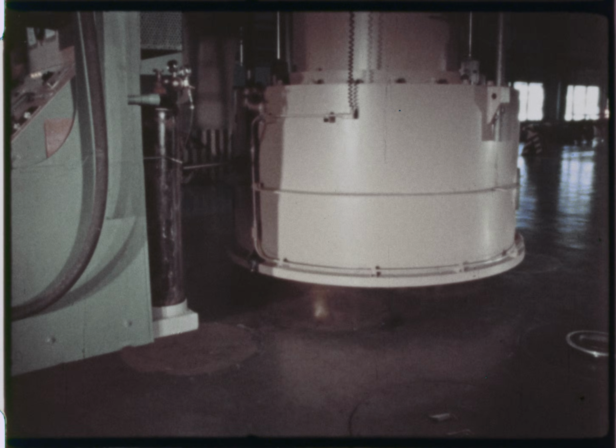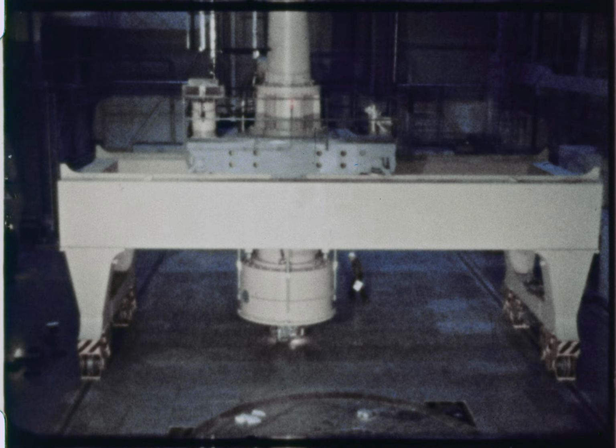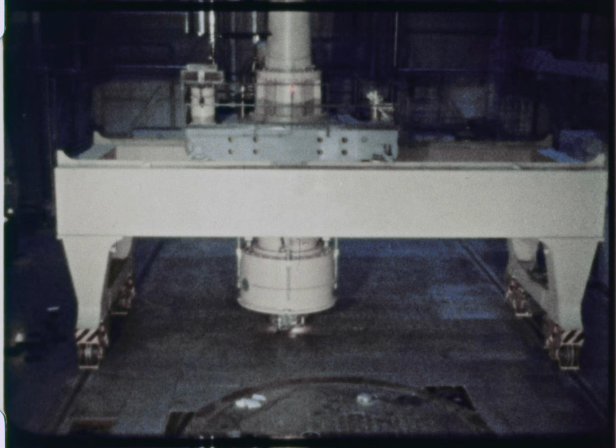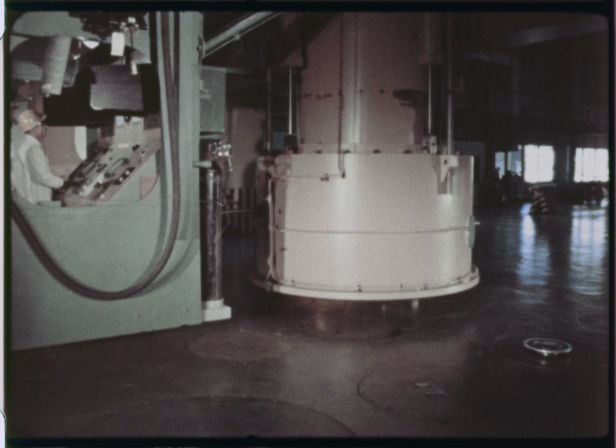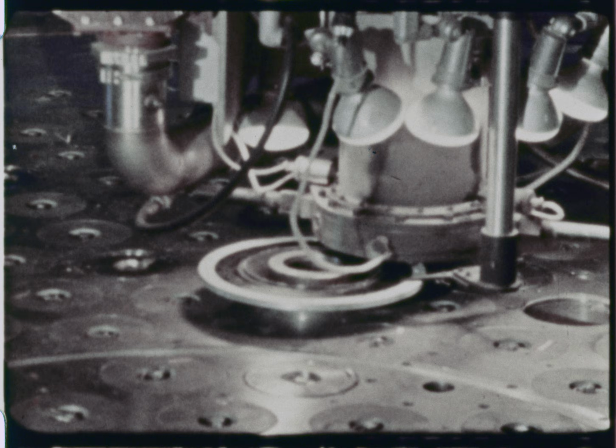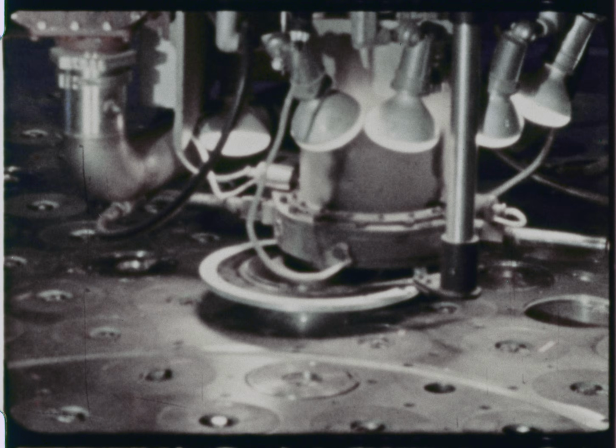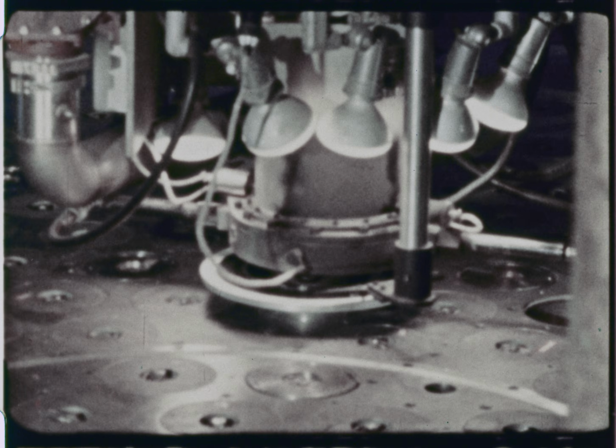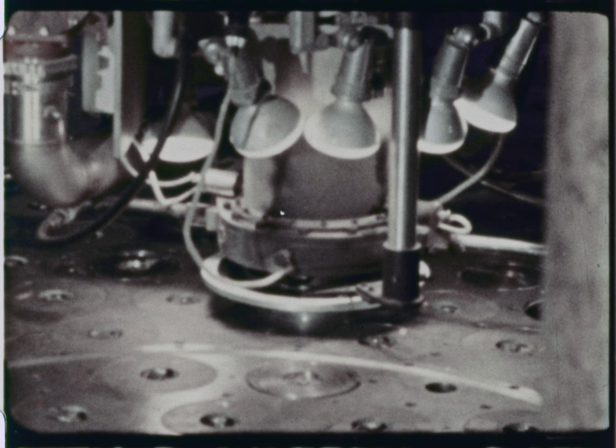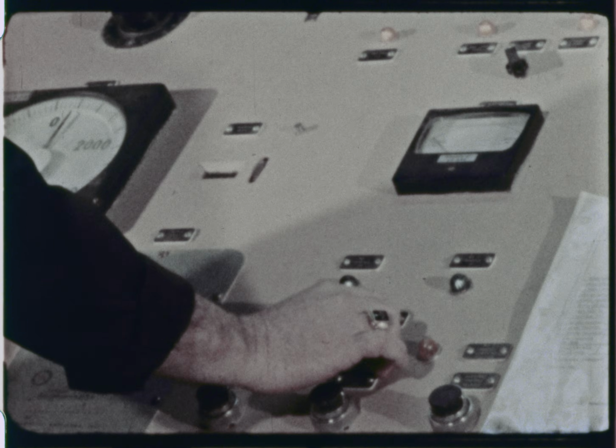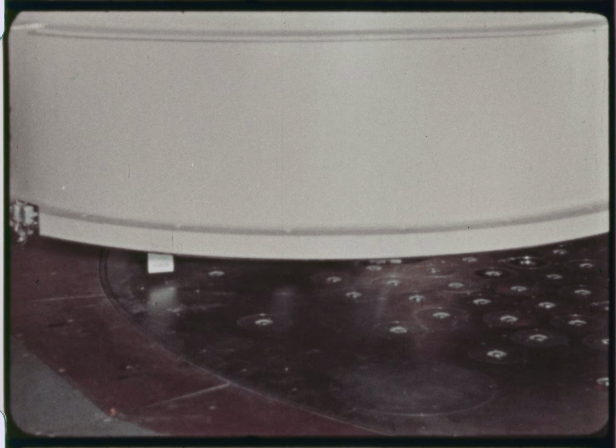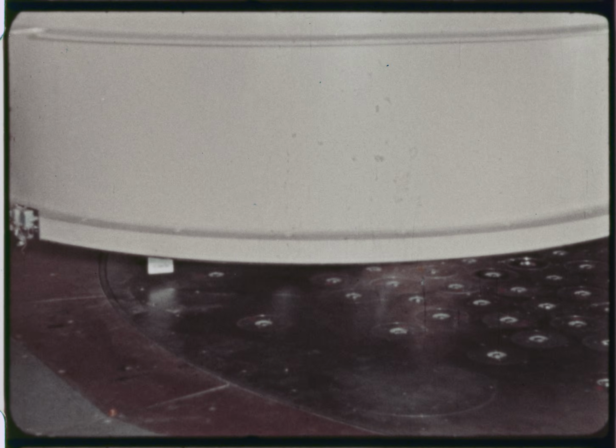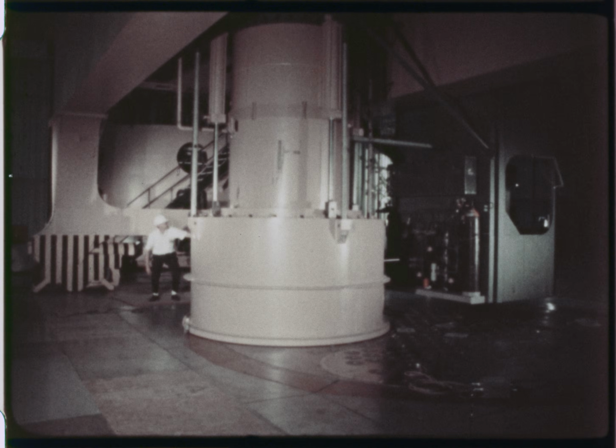The 55-foot high chamber is supported by a gantry crane. When a fuel element is to be changed, a fresh element is picked up from the storage area. The cask is then moved to a position above the reactor. An indexing mechanism moves the cask to a preset position precisely in line with the given fuel element. A pneumatic mechanism forces the lead radiation shield down onto the surface of the loading space. A gas-tight seal is made.